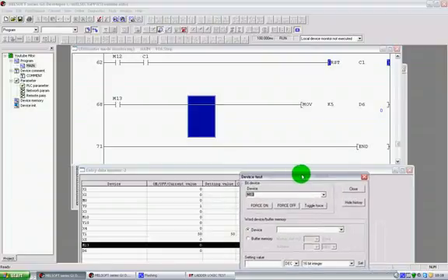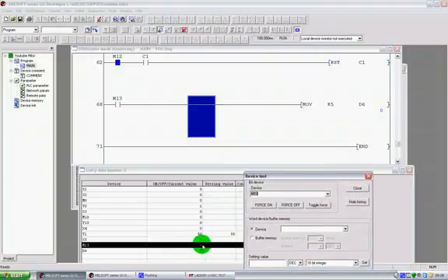If I move it out here, you will see this value change to 1 because it becomes true, and D6 you'll see will have the value that we've moved into it, which is constant. So here we go, and there we go. As soon as M13 went high or became true, we moved that into that. If I force it off, notice how the data stays there.